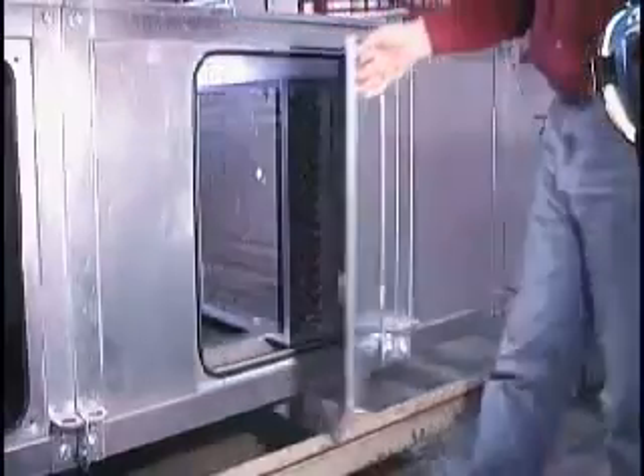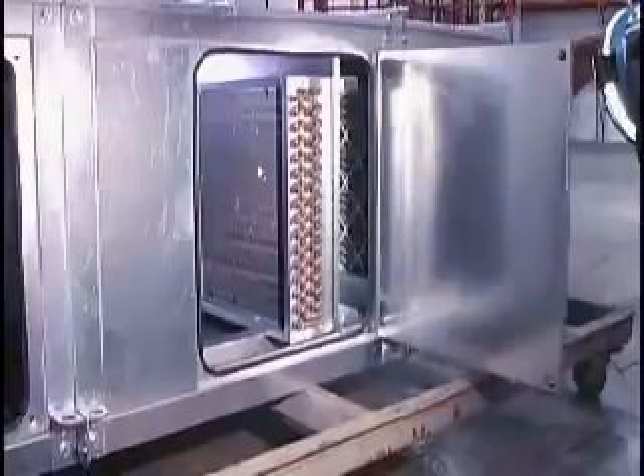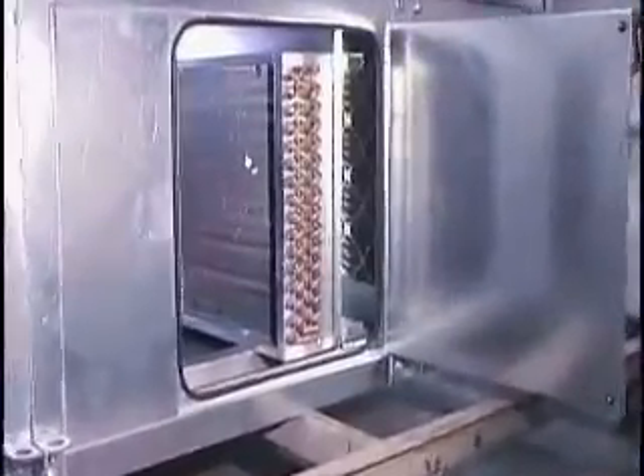After the damper, we need a heating coil in a temperate climate, anywhere up north, the Midwest, the Northeast. Now, remember, as we're talking about this unit is not a big unit compared to a recirculating unit. If the recirculating unit is 100% of the air that's circulated, this unit is only 20%. So we can afford to put the best preheat coil you can think of in there because it's a small coil. Downstream of the heating coil, we normally have the cooling coil. The cooling coil is a special coil.